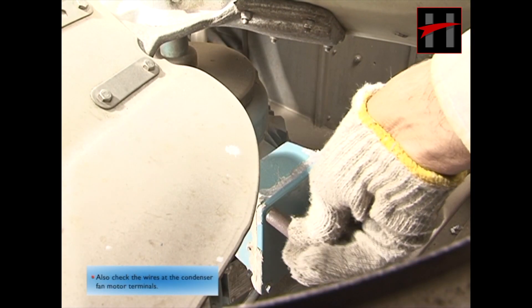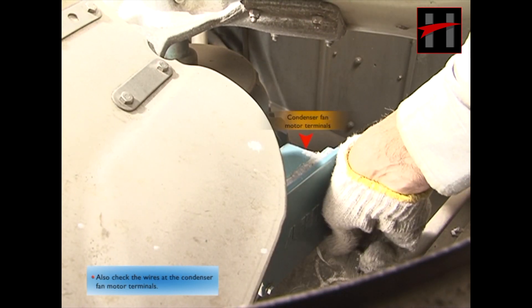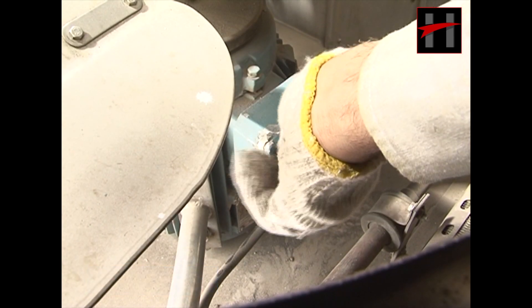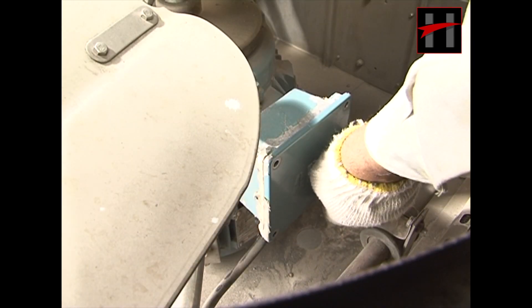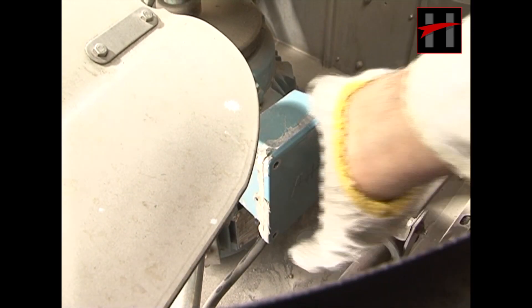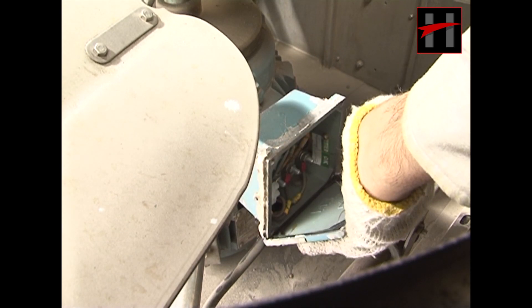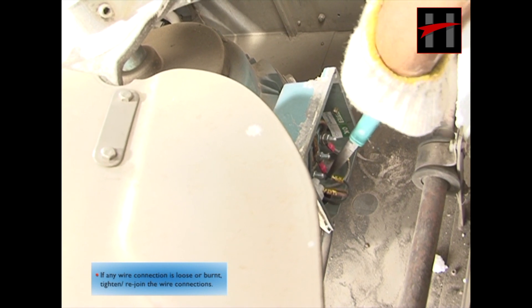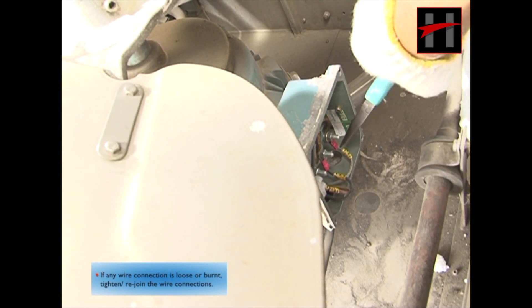Also check the wires at the condenser fan motor terminals. If any wire connection is loose or burnt, tighten or rejoin the wire connection.